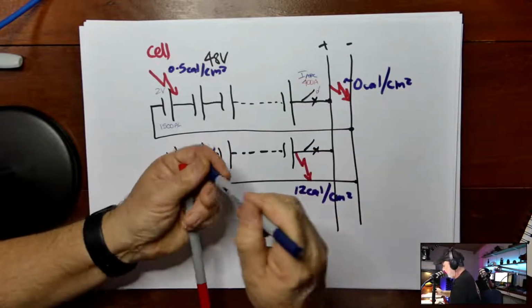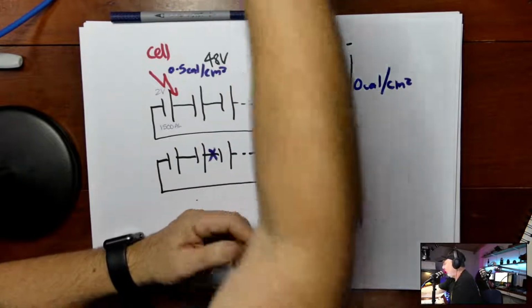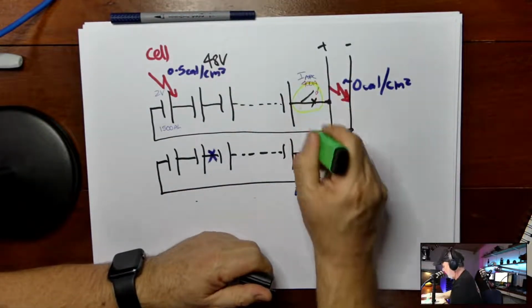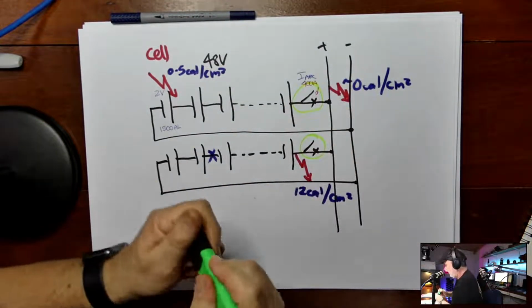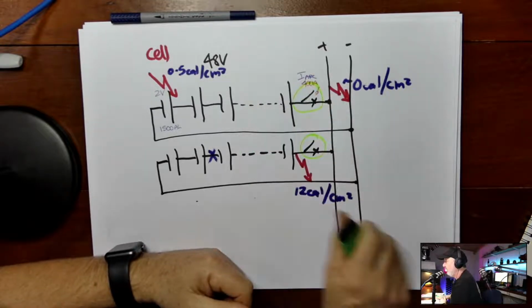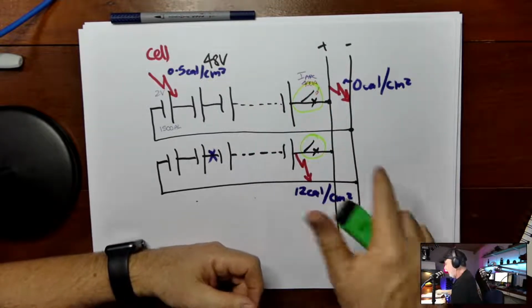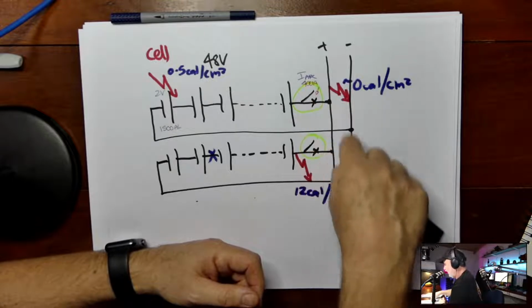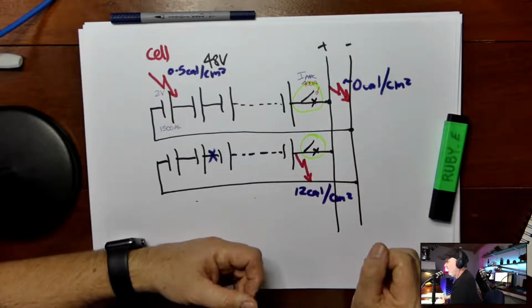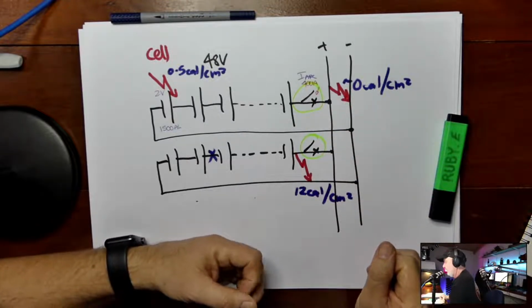And that was all because we put in those interstring overcurrent protection devices here. So that's a big plus. Now, it's a requirement when you've got more than one string. If you've only got one string, it's not a requirement, but it can help with reducing the arc flash incident energy further downstream from the batteries.